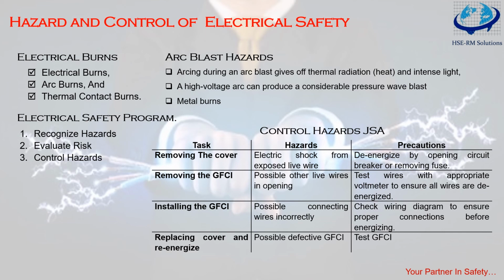Now, removing the GFCI, there's a possibility of other live wires being exposed while opening - that's the hazard. And what are the precautions? Test the wire with an appropriate voltmeter to ensure all wires are de-energized, and install GFCIs, ground fault circuit interrupters.